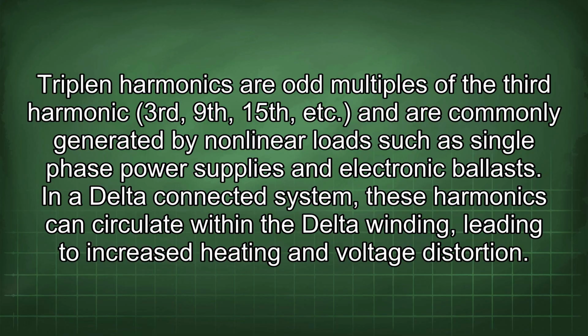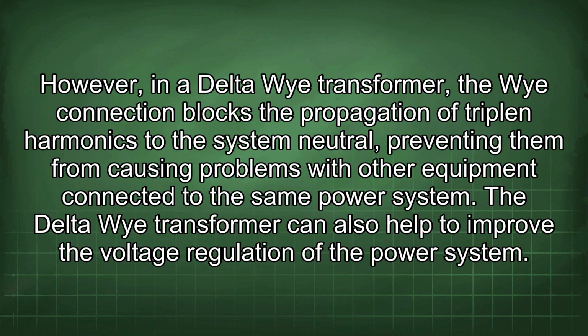In a delta-connected system, these harmonics can circulate within the delta winding, leading to increased heating and voltage distortion. However, in a delta Y transformer, the Y connection blocks the propagation of triplen harmonics to the system neutral, preventing them from causing problems with other equipment connected to the same power system.